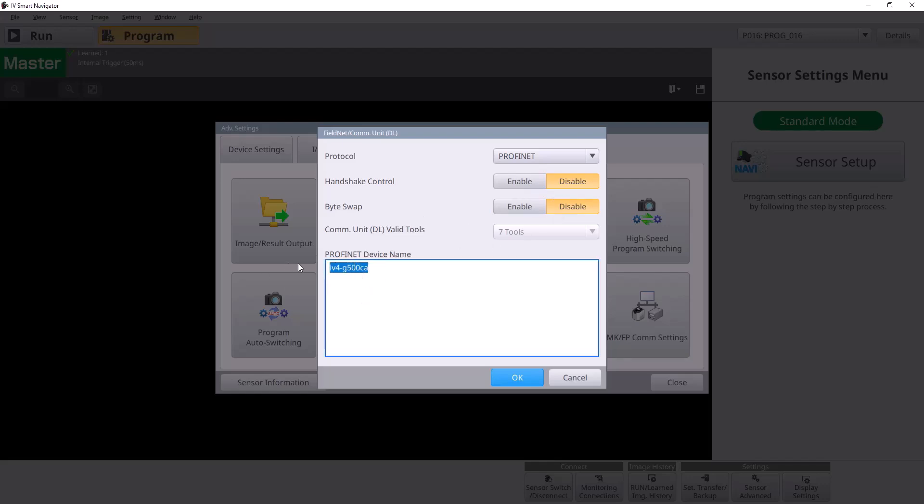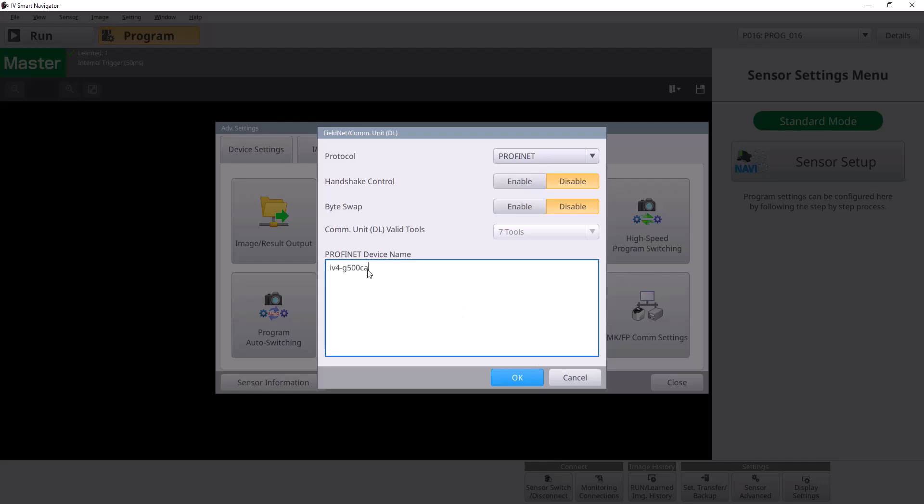You'll also need to give your IV4 a PROFINET device name. You can name it whatever. I just named it IV4-G500CA, which is the model of camera that I'm working with today. The important thing here is you actually have to make sure all these letters are lowercase or not capitalized. It will not accept capital letters in PROFINET.